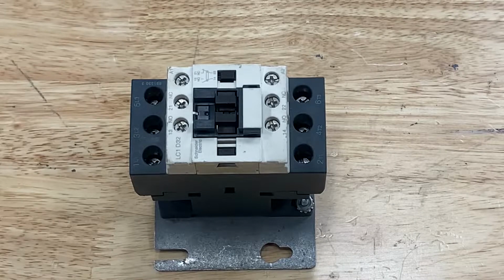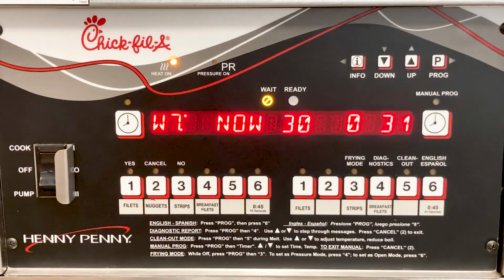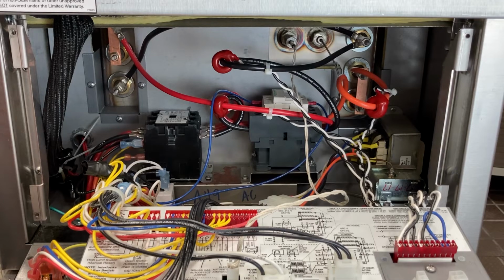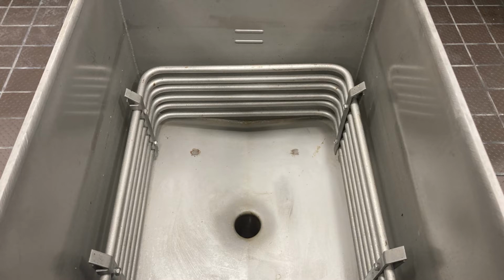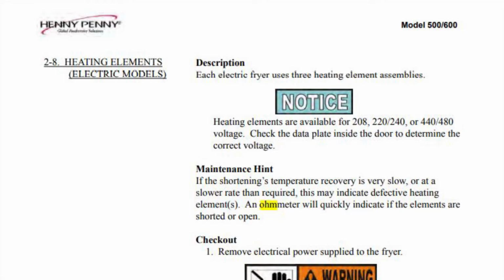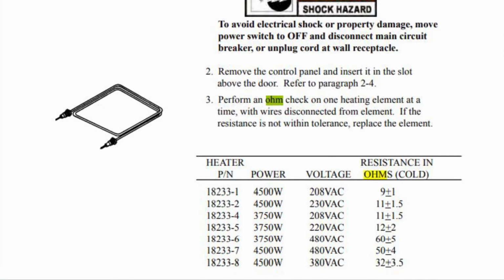If the contactor checks OK, we know the sensors are reading properly, and if visual checks are good, then we could have a bad element and proceed with a resistance check of the element in question. Please refer to the tech manual for proper element resistance values.